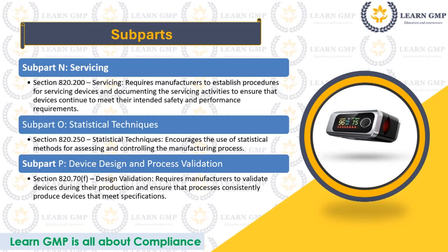Subpart P, Device Design and Process Validation. Section 820.70, F, Design Validation, requires manufacturers to validate devices during their production and ensure that processes consistently produce devices that meet specifications.